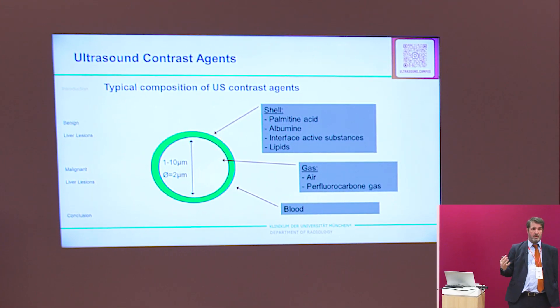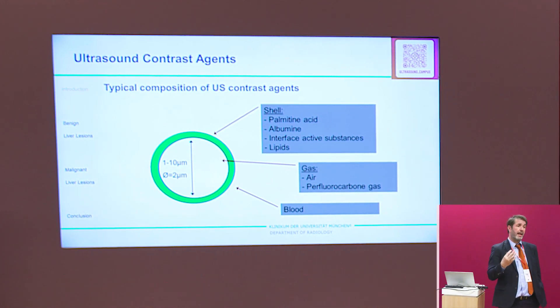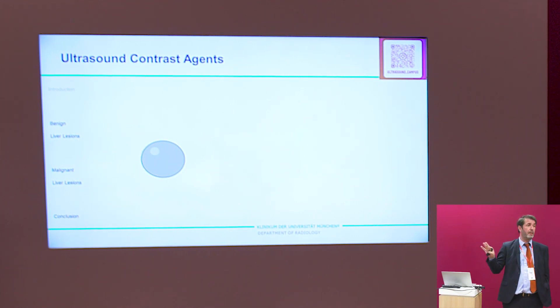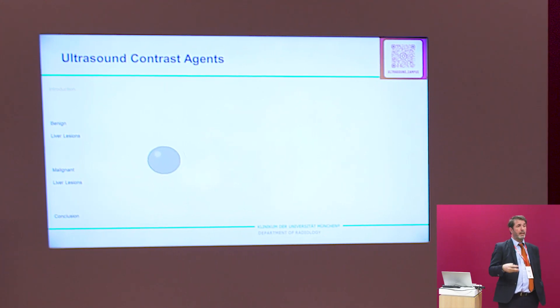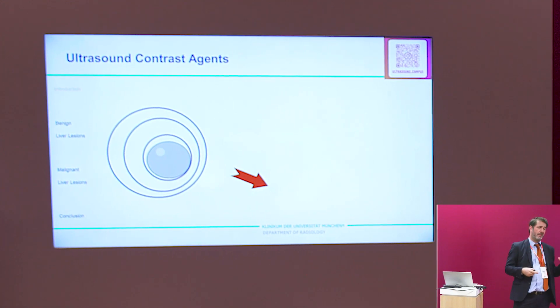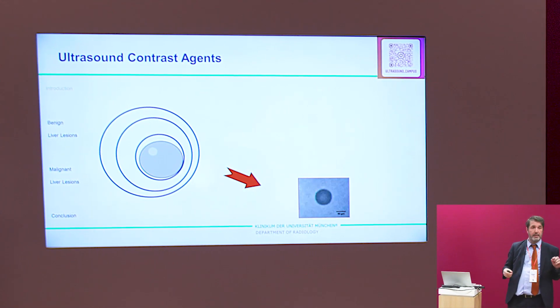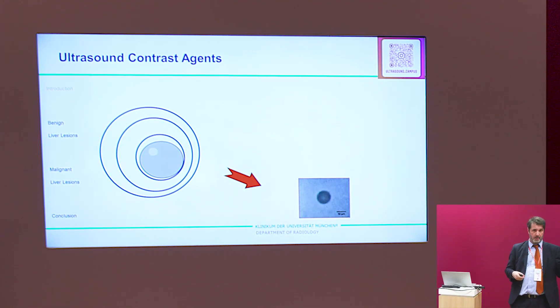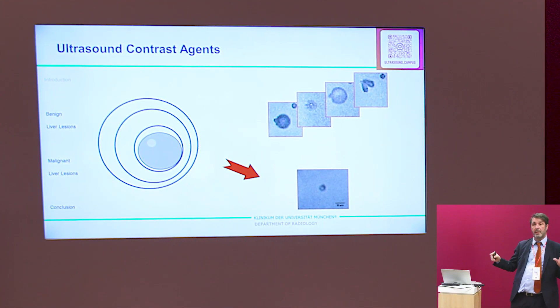In CT or MRI, there is diffusion of contrast into surrounding tissue, so certain lesions can enhance on CT or MRI that will never enhance on ultrasound — because bubbles won't enter unless there is an active hemorrhage. The ultrasound wave from the probe compresses and decompresses the bubble, which acts as a backscatter, giving up to 30 dB more signal. You need special software; otherwise the bubble will immediately destroy and you have no benefit.